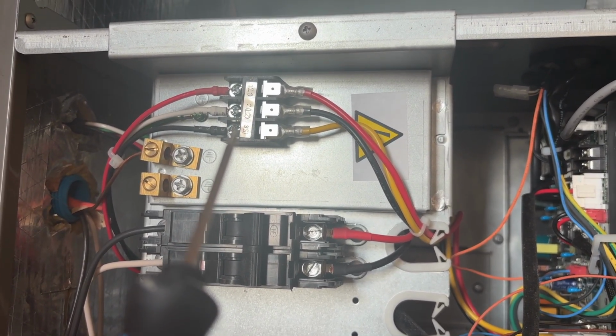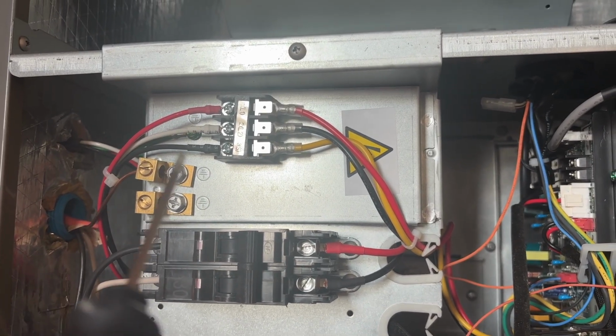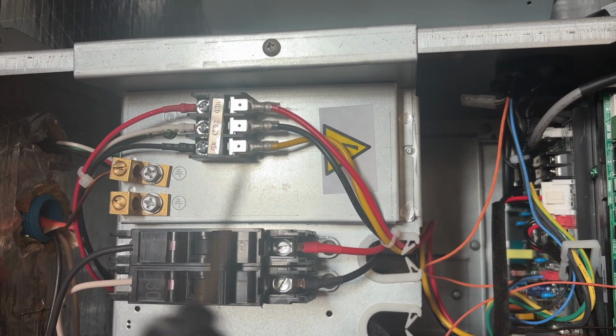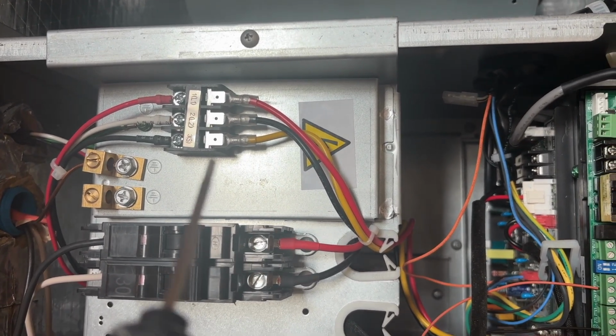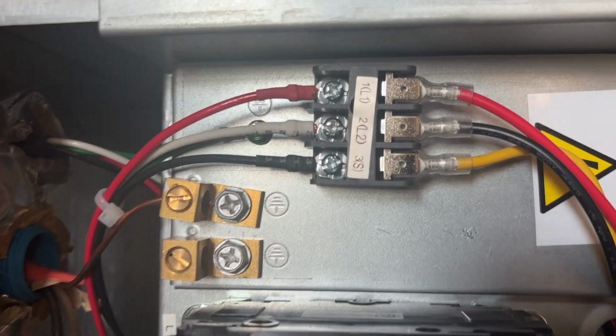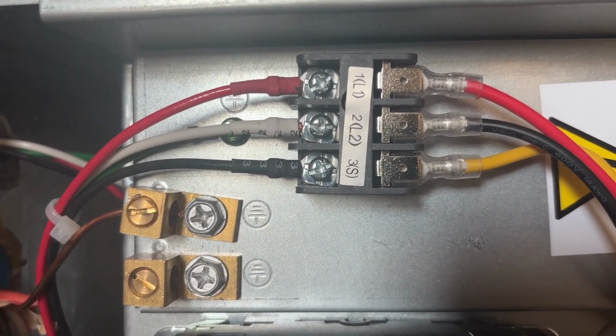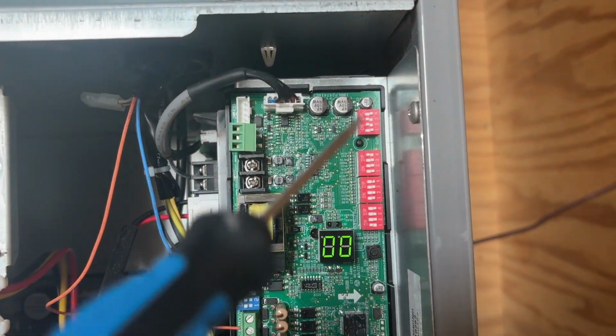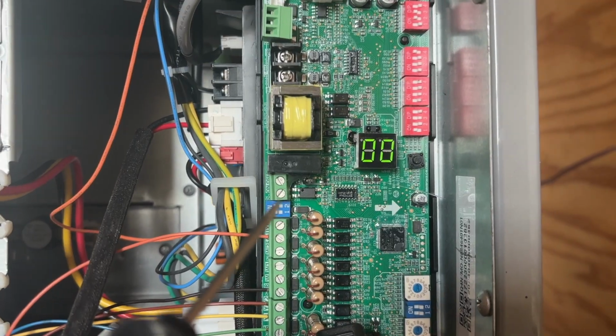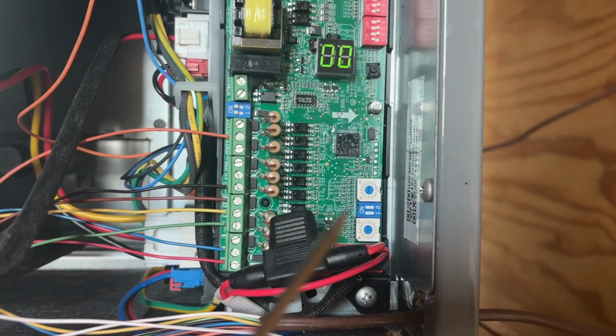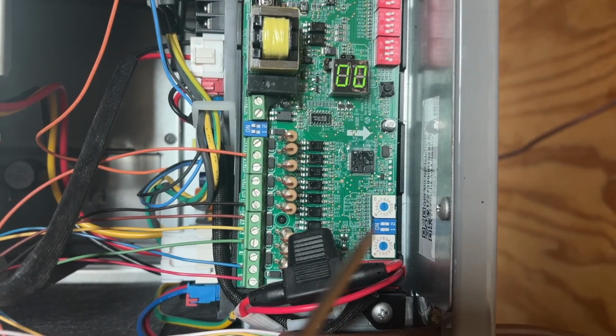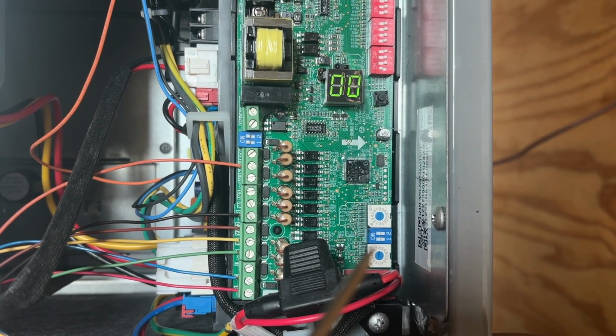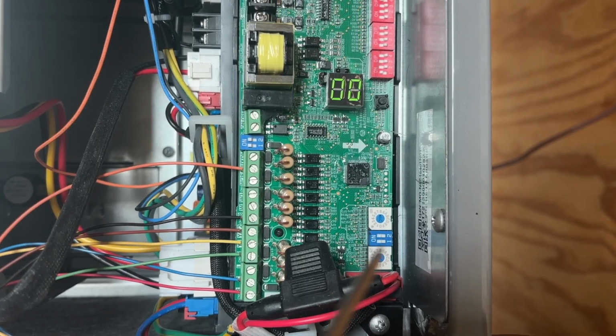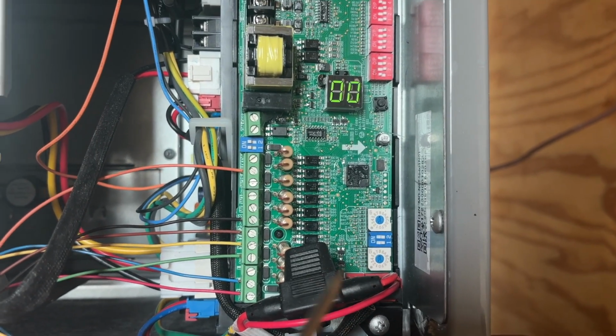This is the signal and power lines from the outdoor unit. This indoor unit gets power from the outdoor unit. So we have power there, and then we have the signal line, which is the yellow running across there. So line 1, line 2, and 3, which is the signal. And then we've already talked about the dip switches we have set. We have the 24-volt bar turned on, and I'm not using any of this. We talked about that briefly. I'm not using any of the outside air temperature stuff. I'm letting my thermostat do all the work, so I've disabled that here.